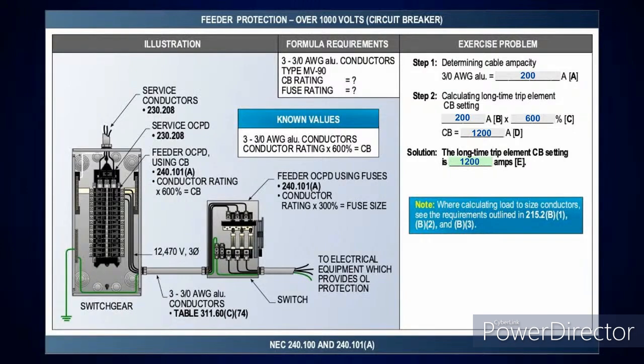And when you look at this in 240.101A, that got moved in the next cycle. I'm not going to get too much into that because, if I'm not mistaken, I think it moved over in 245.27. I think that's where it moved, because that's where they created a new one that talks about overcurrent protection for systems rated over 1,000 volts. I think the new one's 245.27A, if I'm not mistaken.